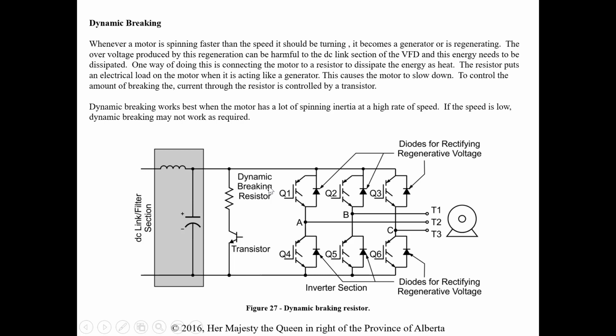This causes the motor to slow down. To control the amount of braking, the current through the resistor is controlled by a transistor. So this guy right here. Dynamic braking works best when the motor has a lot of spinning inertia at a high rate of speed. If the speed is low, dynamic braking may not work as required. Okay, so that's just in general, to have an idea about that. Line regenerative braking captures the energy produced by the decelerating motor and sends it back to the system. Dynamic braking dissipates heat while regenerative braking recycles the energy. So the big difference between the two, again, with these terms, just concentrate on the differences as much as what they're actually doing.